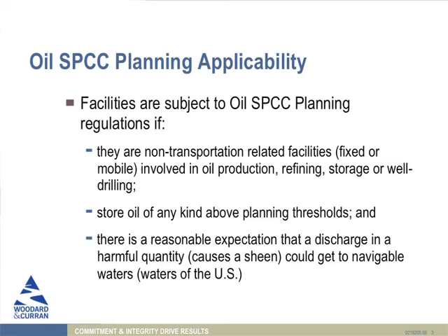So the applicability. These rules do not apply to everybody. You have to meet certain criteria to be covered under this program. First of all, if you are a non-transportation related facility involved in oil production, refining, storage, or well drilling. And campuses, of course, fall under the oil storage provision. If you store oil of any kind above the planning thresholds, and we'll talk about what SPCC regulates as an oil and what the thresholds are in just a moment, and if there's a reasonable expectation that a discharge in a harmful quantity could reach navigable waters.